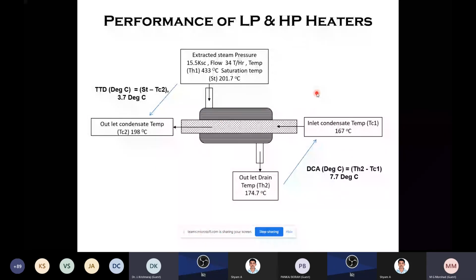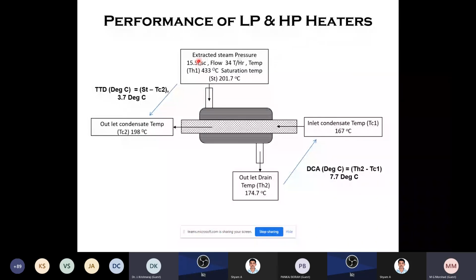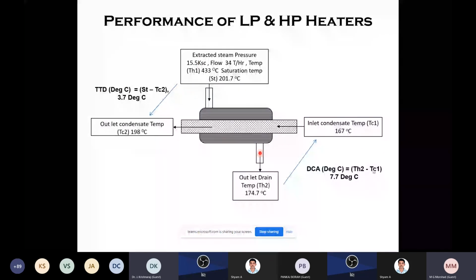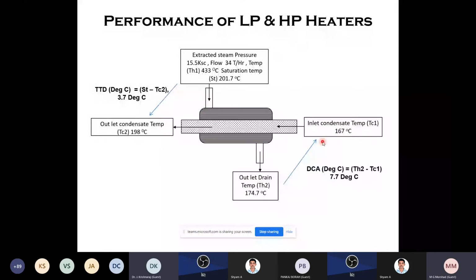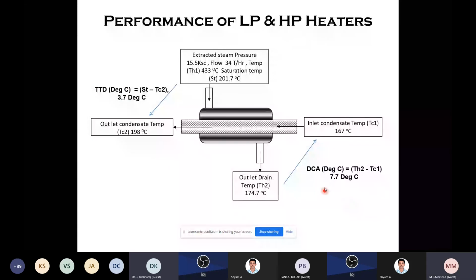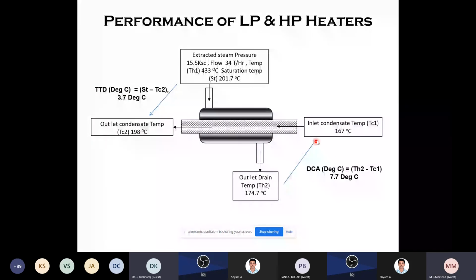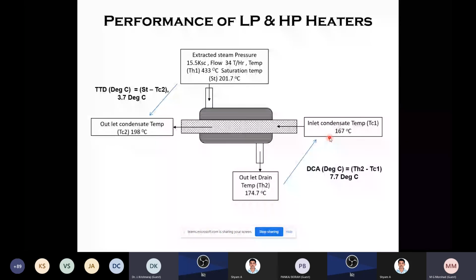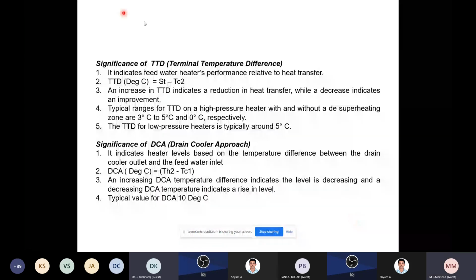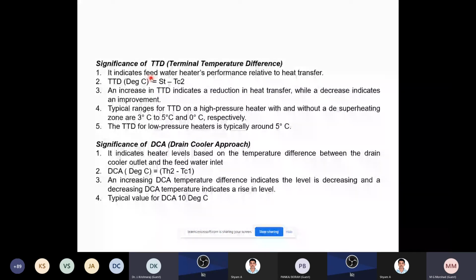So normally the performance of this will be measured by the TTD, the terminal temperature difference, or by the drain cooler temperature. The difference between the extraction steam temperature, at its pressure, and the outlet water temperature is called the TTD. And for the drain cooler, it is the condensate outlet compared to the inlet water. So we can measure both ways. TTD is the better way of calculating performance, so normally we are measuring the TTD.